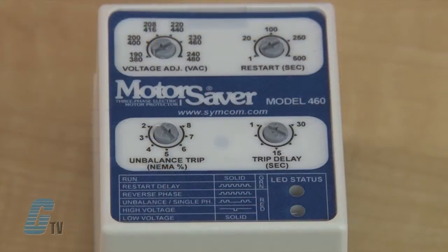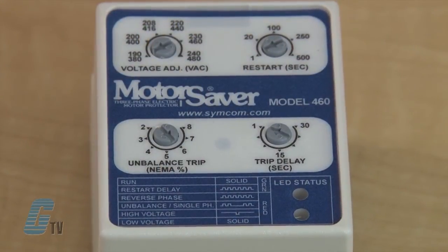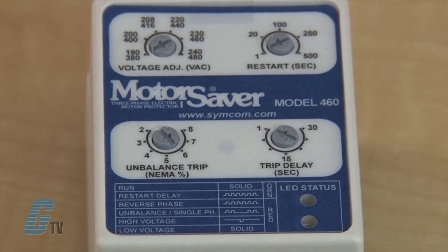An adjustment is provided to set the nominal line voltage from 190 to 240 or 380 to 480 volts AC. Other adjustments include a 1 to 30 second trip delay, 1 to 500 second restart delay, and 2 to 8 percent voltage unbalanced trip point.